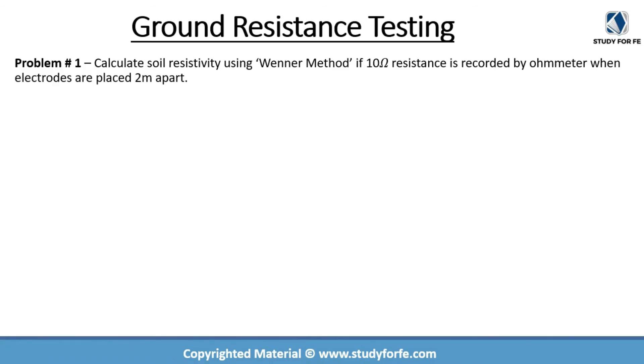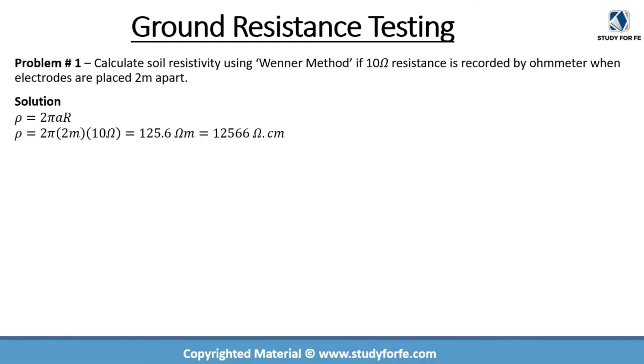Let's go through practice problems on ground resistance testing. Problem one asks us to calculate soil resistivity using the Wenner method if 10 ohm resistance is recorded by the ohm meter and the electrodes are placed 2 meters apart. Using the simplified Wenner equation with R = 10 ohms and A = 2 meters, the soil resistivity calculates to 125.6 ohm-meter, or 12,566 ohm-centimeter.